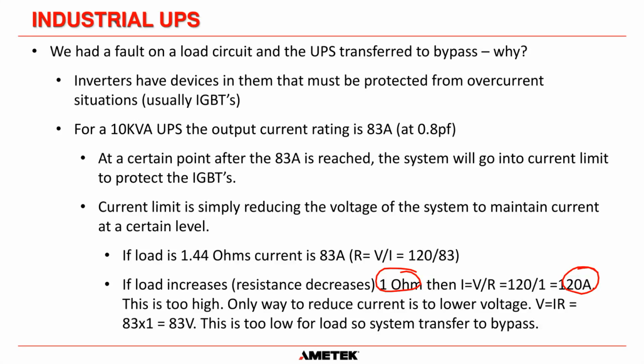That's going to blow up the IGBTs. So the only way that we can protect the IGBTs is to reduce the voltage out of the system to reduce the current. So remember, volts is equal to amps times resistance. Therefore, we would have to reduce the volts to 83 amps times the resistance, which is 83 volts. Now, in most circumstances, that is going to be too low for the loads to stay good. So the static switch will monitor this voltage, and if it sees it go that low, it will usually cause the system to transfer to bypass. But the main reason it does all of this is to protect the IGBTs, those 100 amp IGBTs that I mentioned. That's what we're trying to protect.